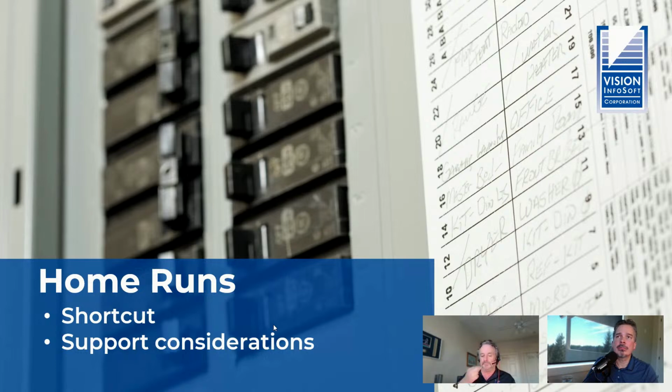Let's say, again, we need 10 circuits for the lighting home runs. So we'd put a total of 600 feet in, 10 runs for all the lighting home runs. So again, you take the number of lighting circuits, divide it by 3, take half of the longest dimension on the building, and round it up a little bit. So if we need 10 home runs at 60 feet apiece, it would be 600 feet and 10 runs. The supports on the lighting, I'm going to show you this in EBM, how I would do it.